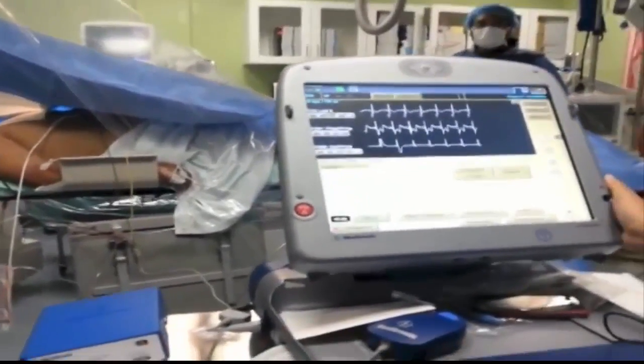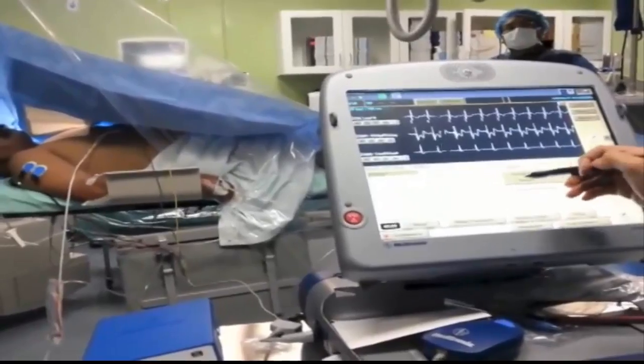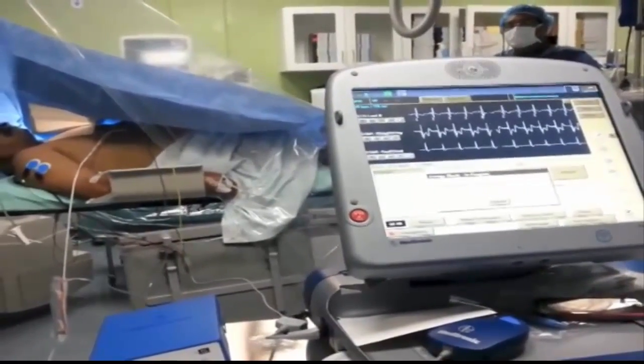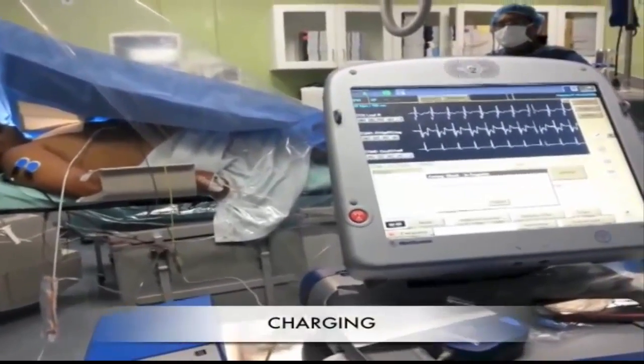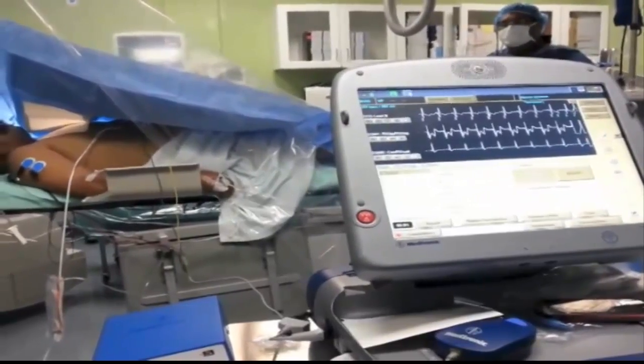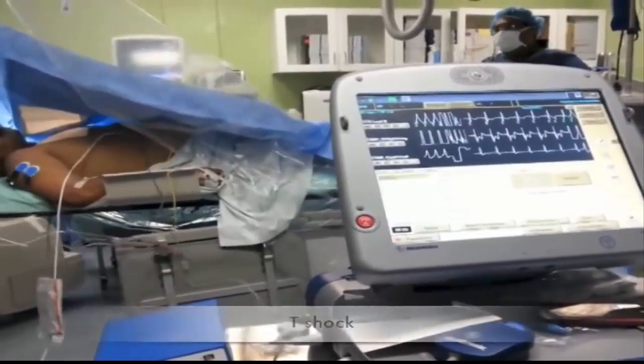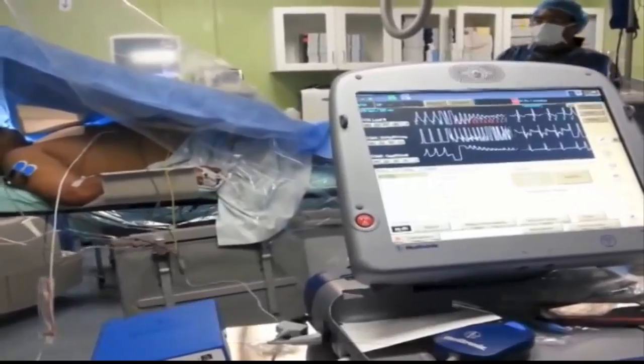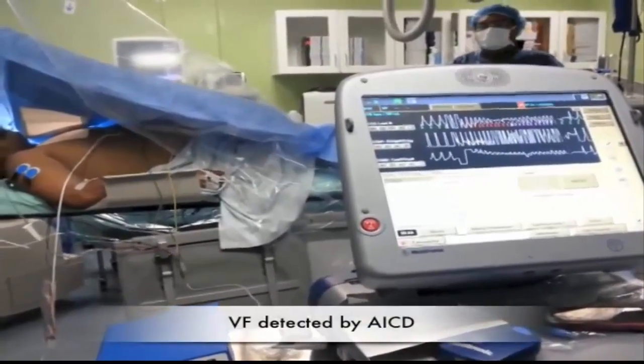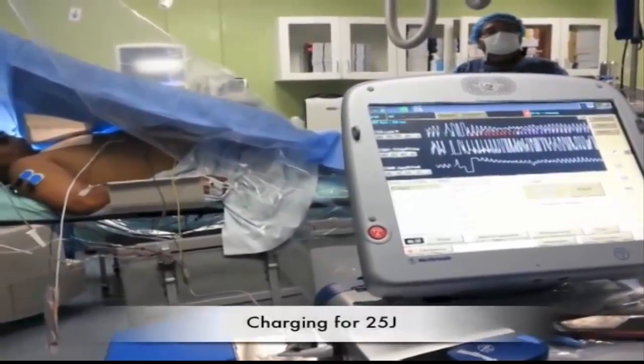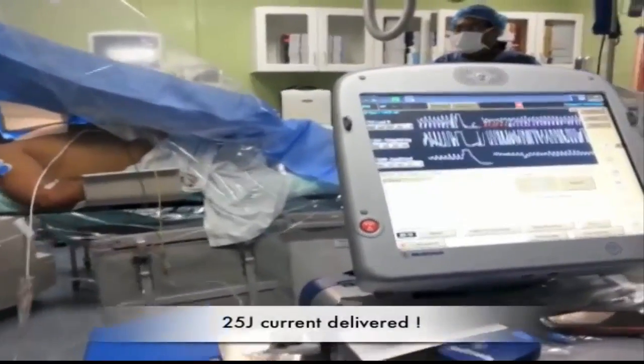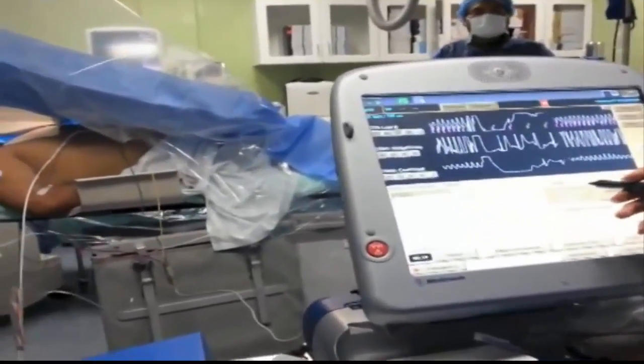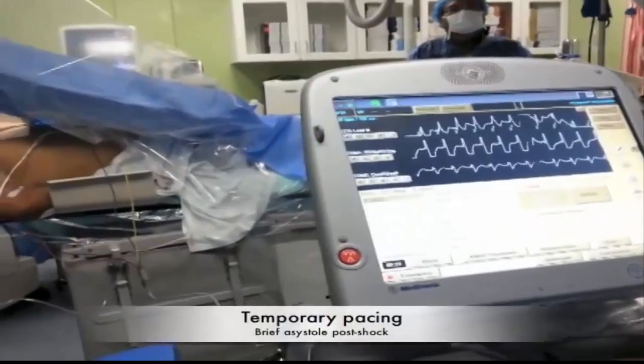So everyone's ready. Charging. Pacing train, T-shock, VF sense, VF detected, charging for 25 joules, charge delivered, back to sinus. Okay, good. Right.